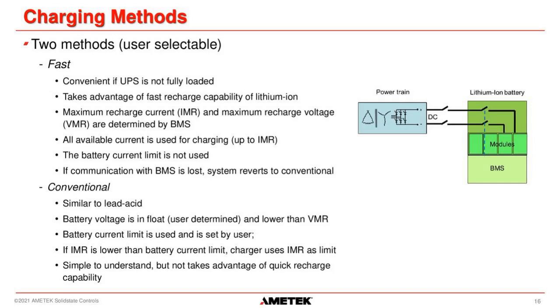So the conventional method is very similar to lead acid that we use currently. The battery voltage is in float, and the user can set what they want the float voltage to be. But if the user sets the float voltage higher than the maximum recharge voltage specified by the battery, then the charger will go to the VMR voltage and not to the user's requested voltage.